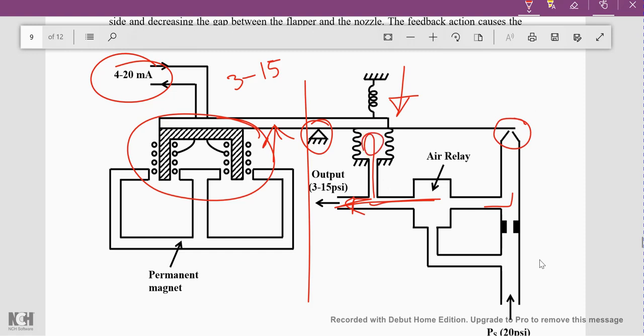This output pressure is sensed with the help of a bellow. If the pressure increases, the bellow expands. The expansion of the bellow helps whatever displacement had changed from the original value to come back to its original value. The increase in output pressure causes the bellow to expand, moving the flapper back to its original equilibrium position, thereby controlling the output to its required value.